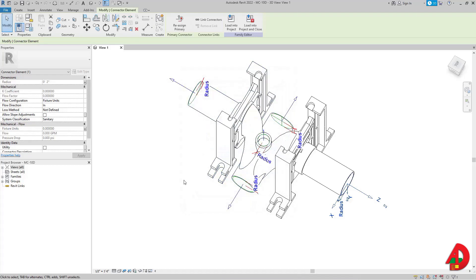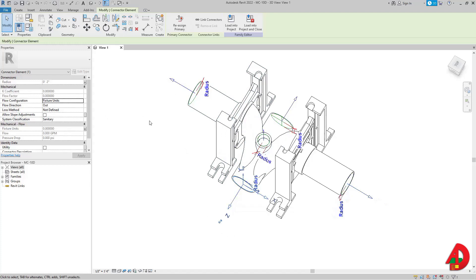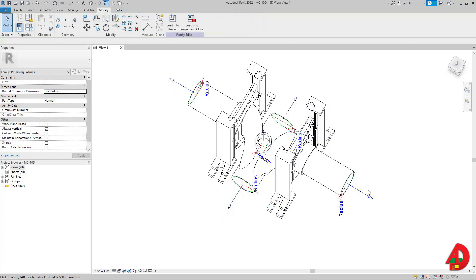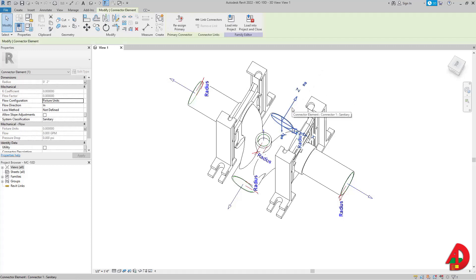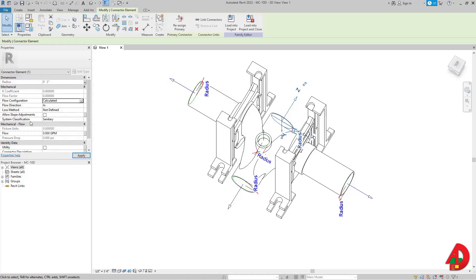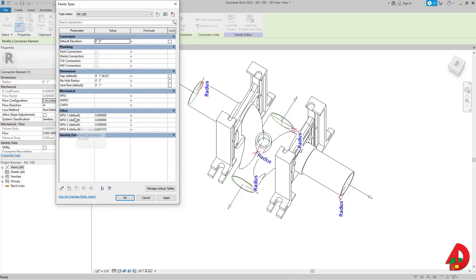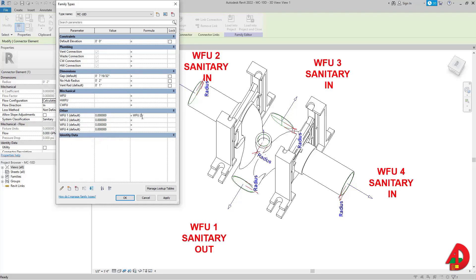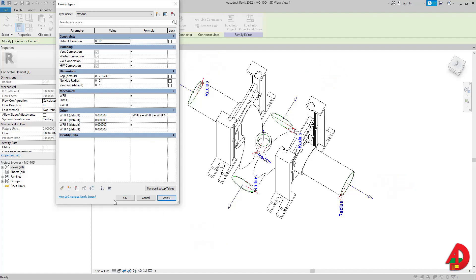Now the system knows it's sanitary and works with fixture units. However, the 'Out' connector needs to compute whatever comes in from the left, the right, and the top — the sum of the other water carriers and water closets. To do that, I change the flow configuration back to 'Calculated,' which grays out fixture units again, but the parameters are still there. I'll create the formula: waste fixture 1 equals waste fixture 2 plus waste fixture 3 plus waste fixture 4, then press Apply and OK.